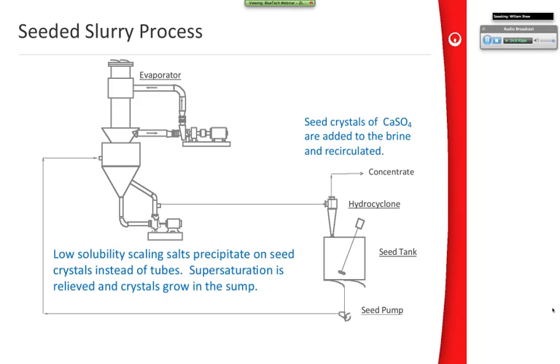The seeded slurry process is a way to control scaling in the evaporators. Typically, we have low solubility salts like calcium sulfate that are present in the brines that are typically concentrated in brine concentrators. So we use seed crystals of calcium sulfate.